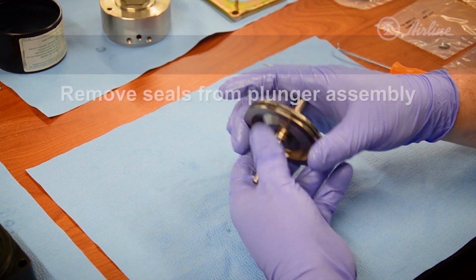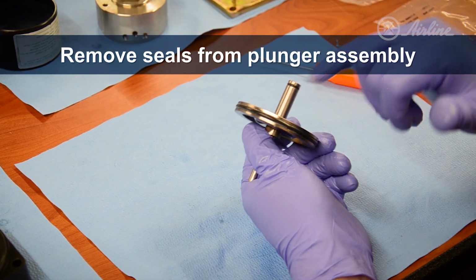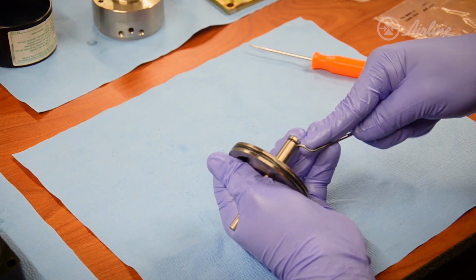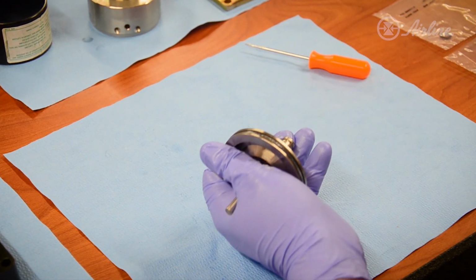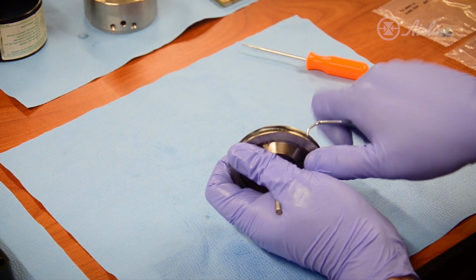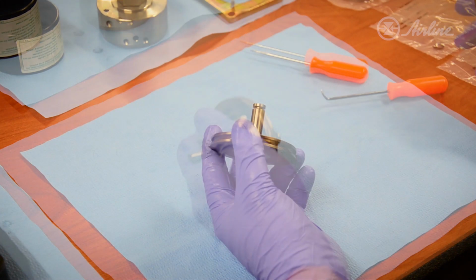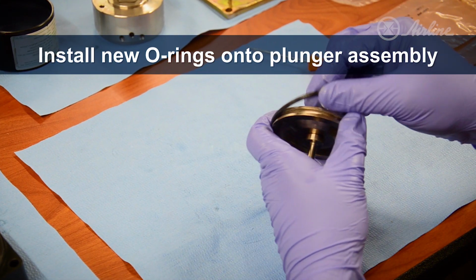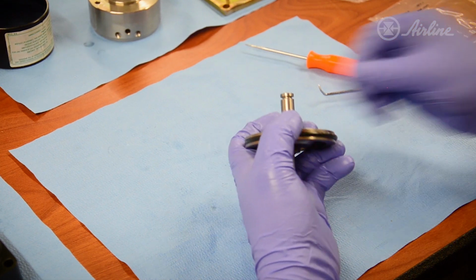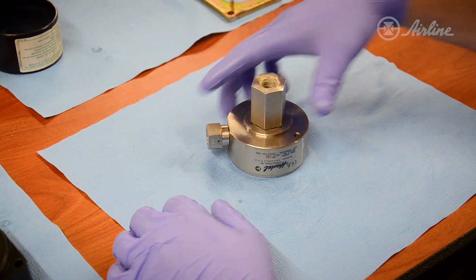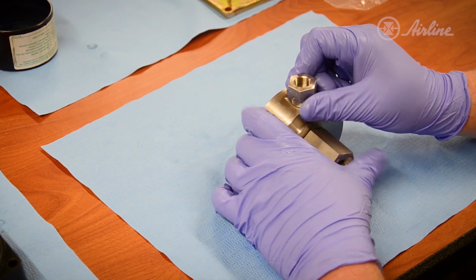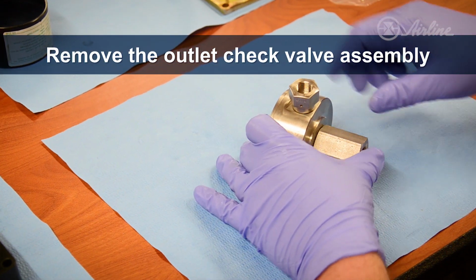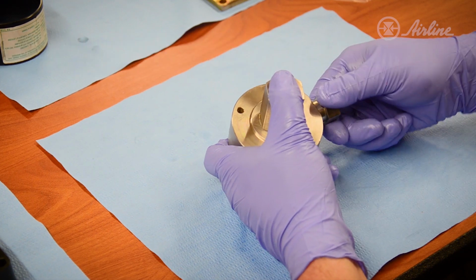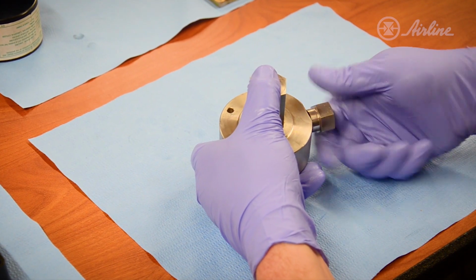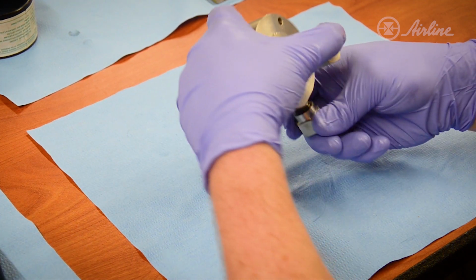Alright, so now we'll replace the seals on the plunger assembly. There's 2 O-rings that need to be removed and replaced on this assembly. After the new O-rings are lightly lubricated, we'll reinstall them on the plunger assembly. And that completes the reseal of the plunger assembly. So now we're going to work on the liquid section. We'll start with removing the outlet check valve assembly. We need to be careful here because there's lots of small parts that need to be kept in the correct order. We'll remove this fitting, which contains all of the check valve components.